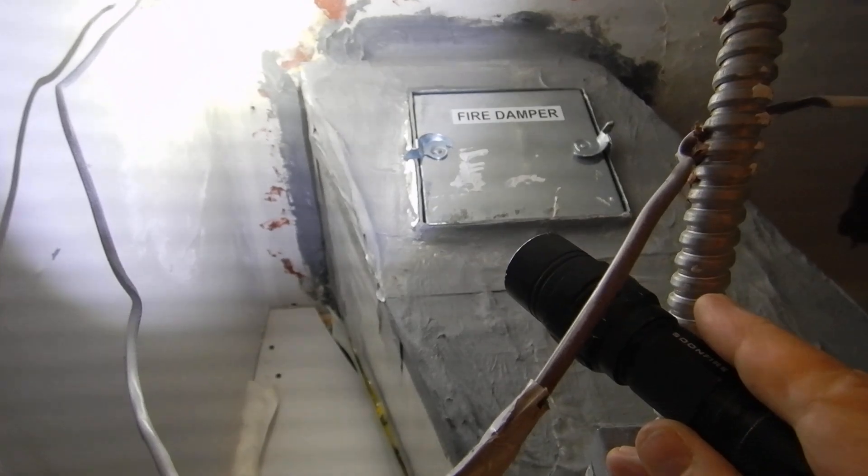Okay, you see those gaps? See these gaps? That compromises the draft stopping. We cared about the draft stopping up here, but now we've got it over there and the tape is coming loose. And then we come over here, draft stopping there, there, there.